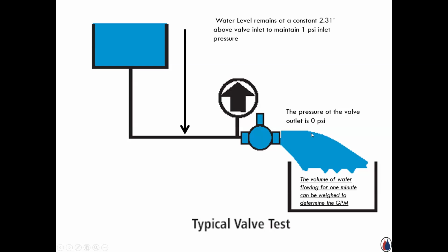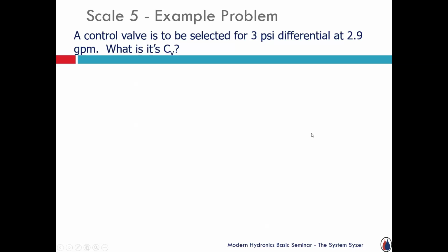So depending upon your application, sometimes you want a lot of pressure drop, and that's called control valve authority. I want to really regulate the output of something by controlling the flow. I want to create good pressure drop. Other times it's almost in the way, it's an open or closed, so I want low pressure drop, so I don't want to eat up all my pump head just on the silly little valve. So it's just understanding that dynamic, that relationship that exists. And it all comes back to this relationship of what's the flow in GPM that causes a 1 pound pressure drop. That's that particular valve manufacturer's CV rating.